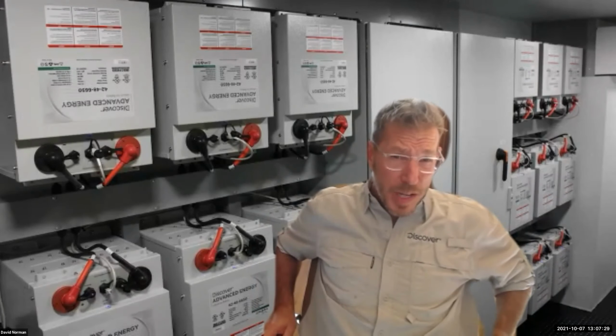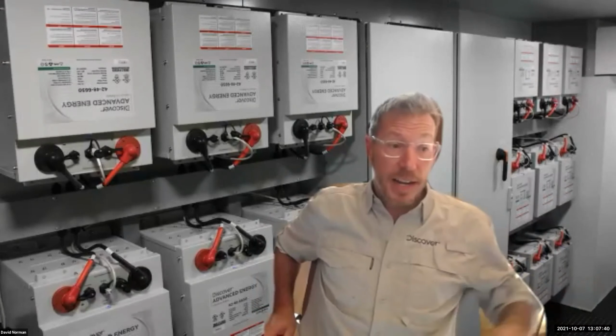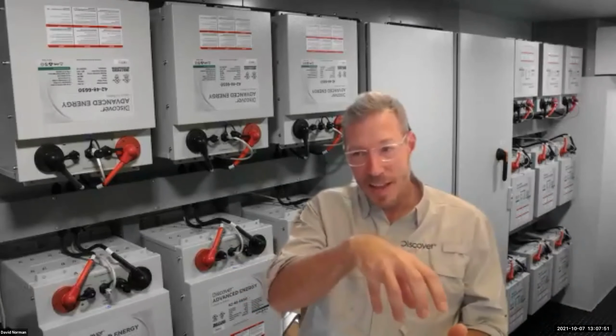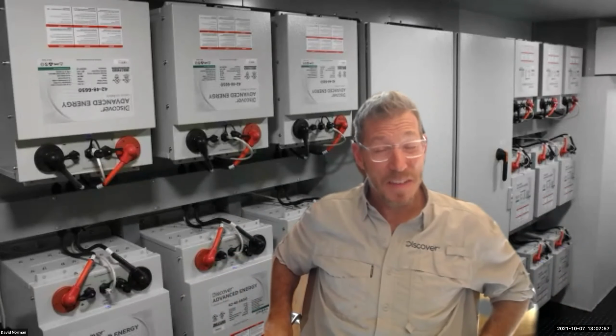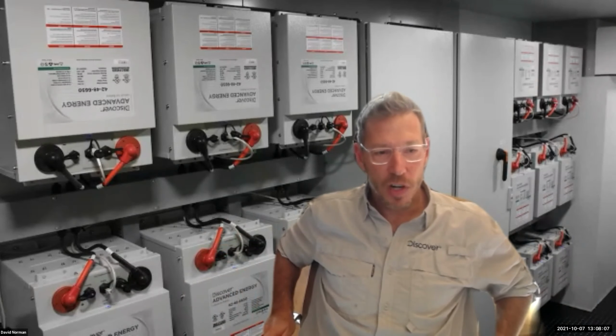that the algorithm we use is in relation to discharge current at the time. It's not simply from voltage, it's from discharge overall, shunted monitoring. It's from the rate of discharge, and it's from the voltage at a cell level, and then obviously each cell series stack of cells, and then the cell block as an average. So there's an algorithmic interpretation there, and it is very, very accurate. It's also load dependent, so our SOC and rate thereof is determined differently at different stages of charge.